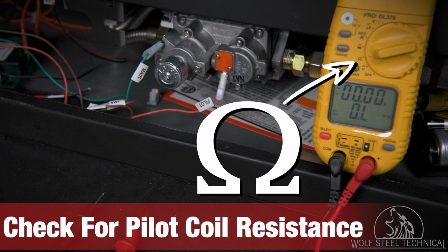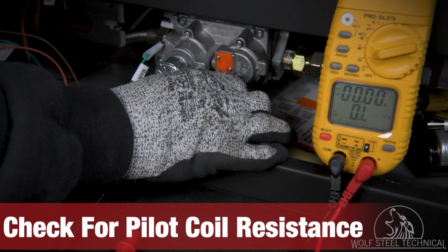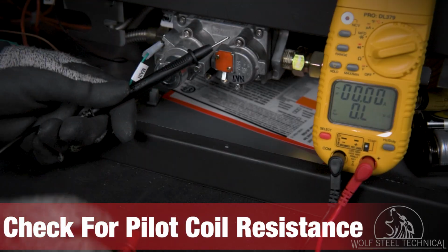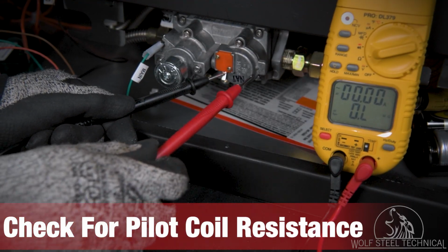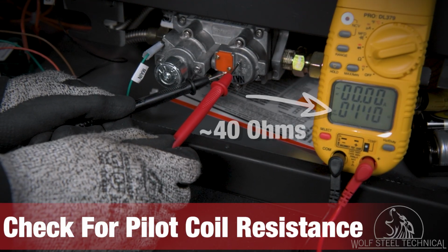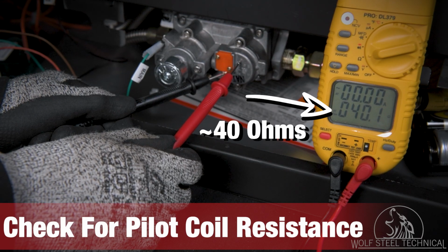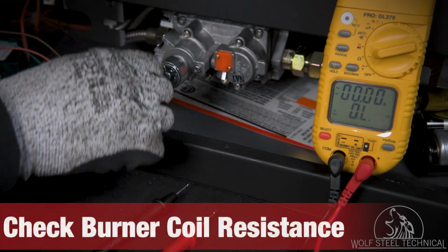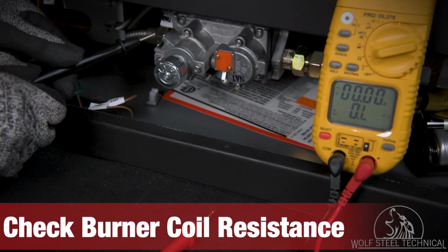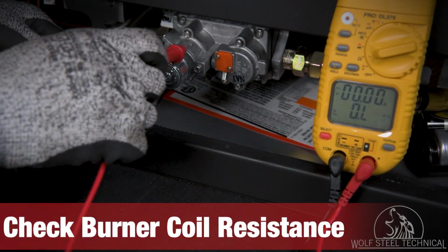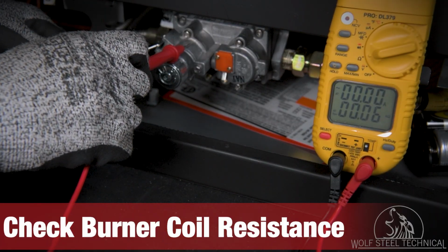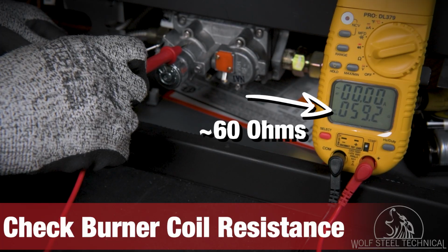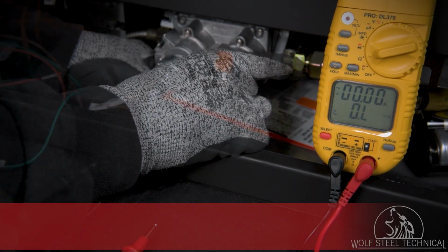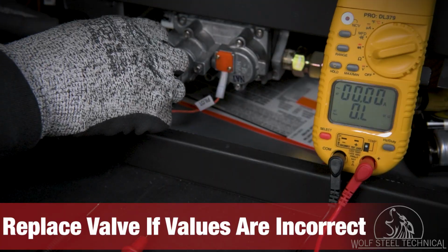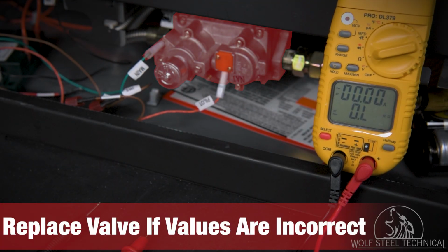Next, set your multimeter to ohms to check for resistance, and turn your attention to the valve. To check the pilot coil resistance, remove the pilot wire from the valve and place the black lead on the pin and the red lead on the valve body. You should receive a reading of approximately 40 ohms. Then, check the burner coil resistance by removing the main wire and placing the black lead on the pin and the red lead on the valve body. You should receive a reading of approximately 60 ohms. If either of these readings don't display the correct value, the valve will need to be replaced.